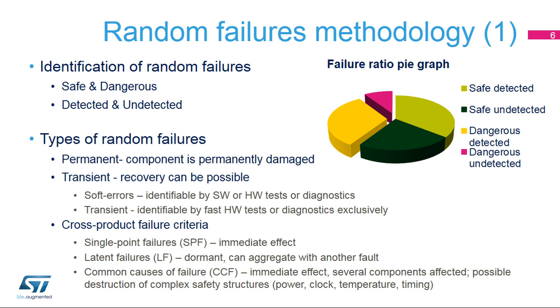Random failures can cause permanent or recoverable errors. Hard failures cause permanent physical damage to the component, and the system is no longer able to operate normally. If no compensation is possible, the system has to be put into a safe state, for example cutting power to actuators, until it is repaired. Random transient or soft errors can be correctable, and some kind of recovery process can be applicable. Soft error failures can be managed by both hardware and software, while transient failures need fast hardware methods exclusively.